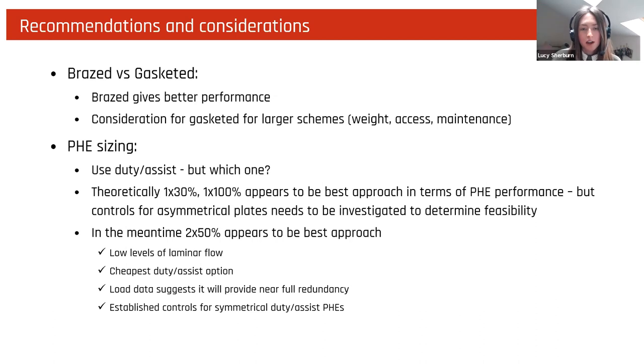Plate heat exchanger sizing. I think it was kind of clear that using a plate sized at 100% is probably not the way to go. So that leaves the duty assist options, but which one? Well, theoretically, using a jockey plate appeared to be the best approach in terms of flow performance, but we haven't really seen this approach used on site or have experience with it. So we need to investigate and determine feasibility of using these asymmetrical plates.